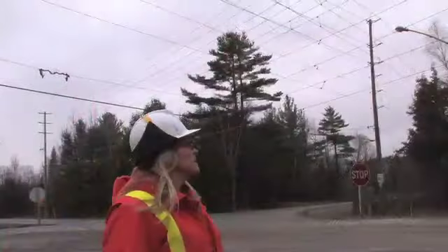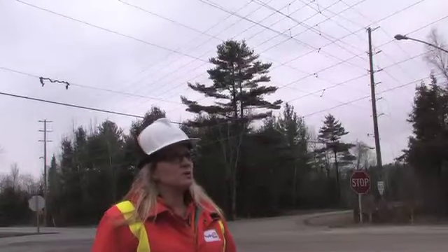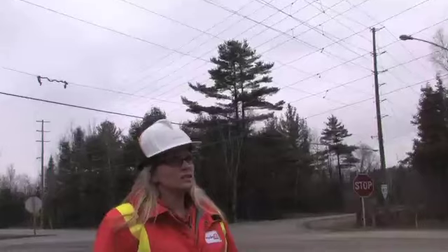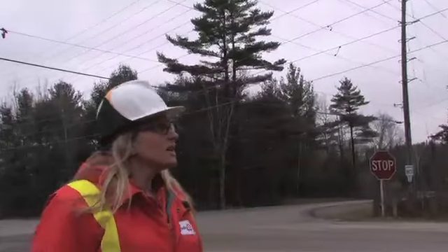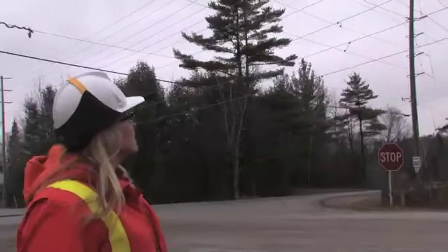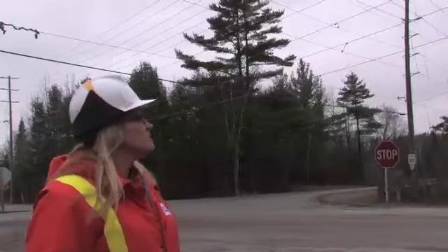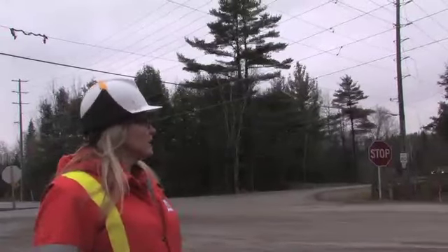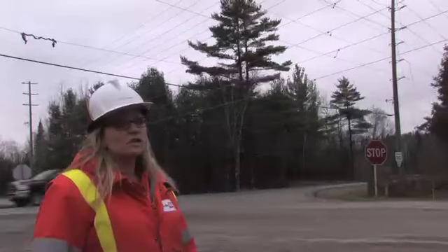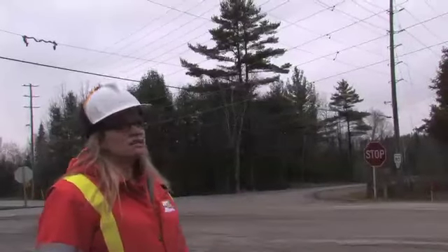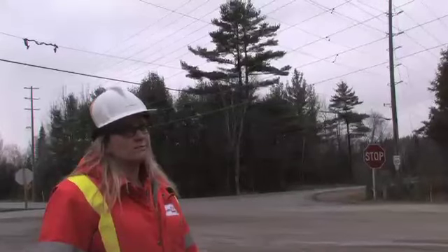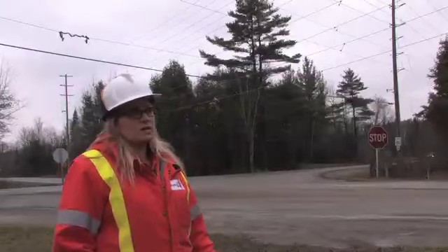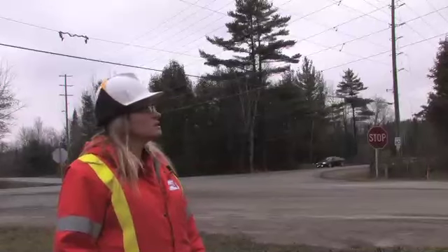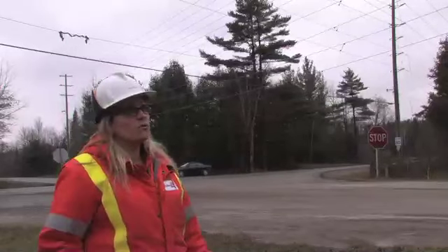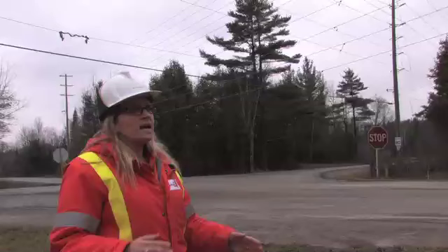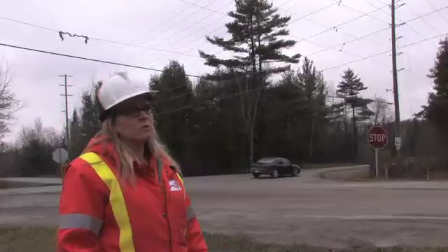This is one of many examples on this job where we've had to get hold of Technical Services for a non-standard application. The line here fly-taps, meaning the lines tap but not on a pole, they tap mid-span. This existing pole does not meet standards for clearances, and it's just not something that would meet Regulation 2204. So Technical Services need to spec for us what the clearances between conductors are, for all four poles surrounding this intersection, and the spacing and height of those poles.